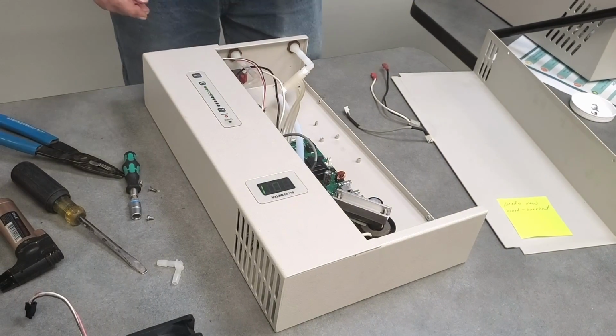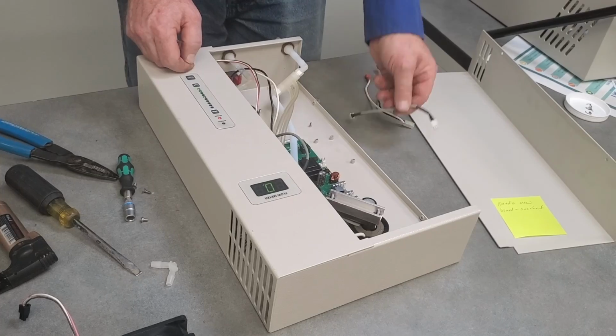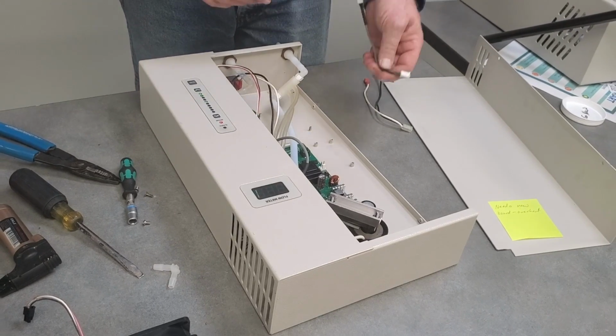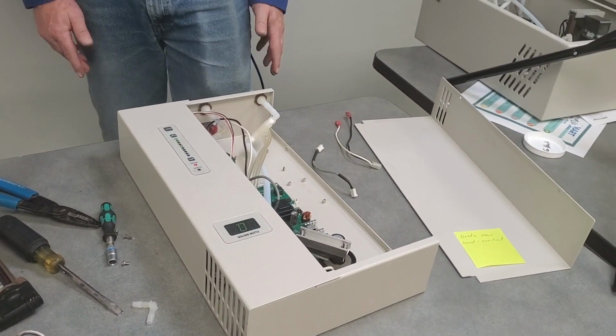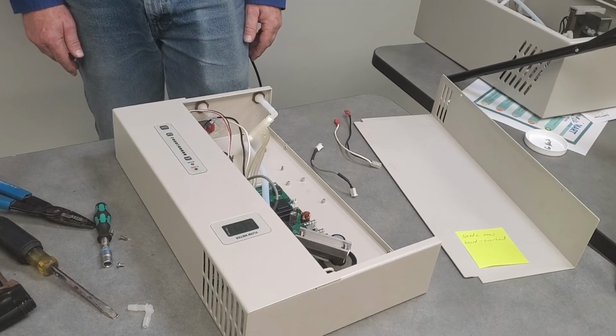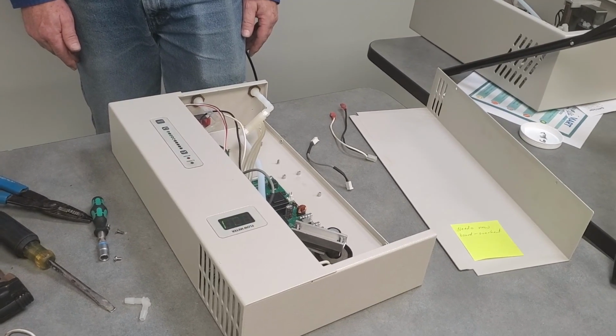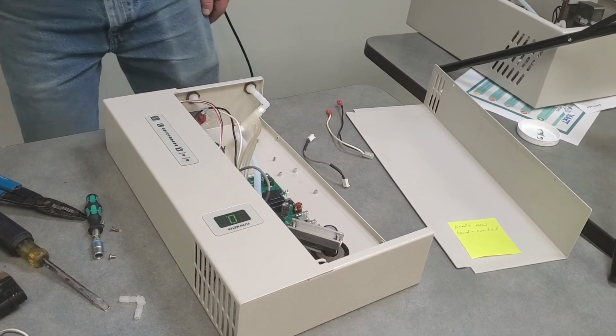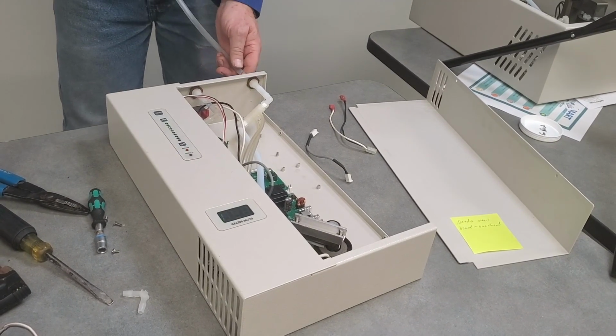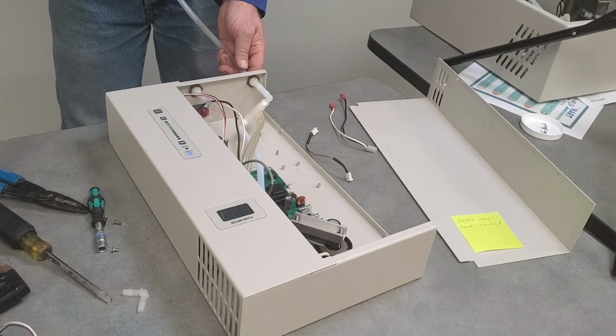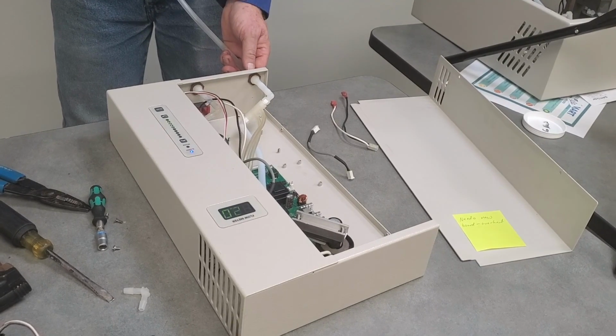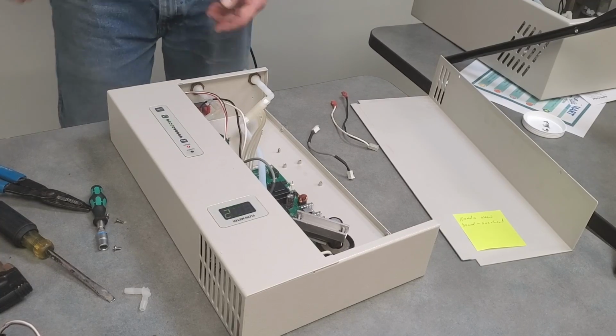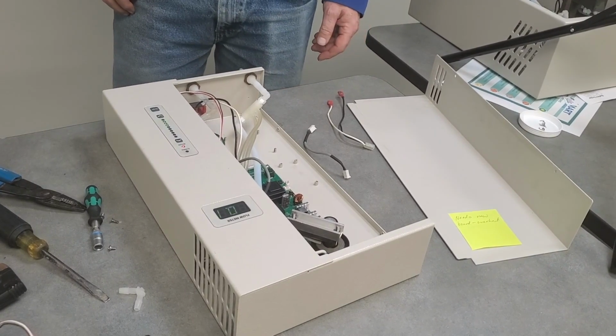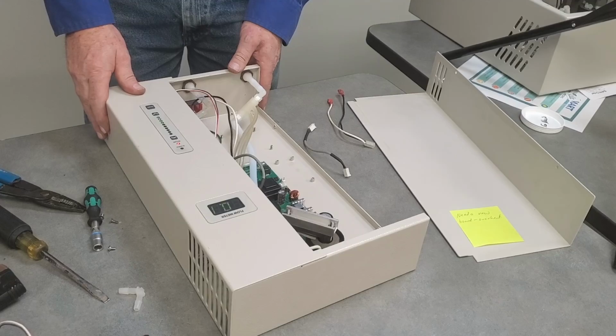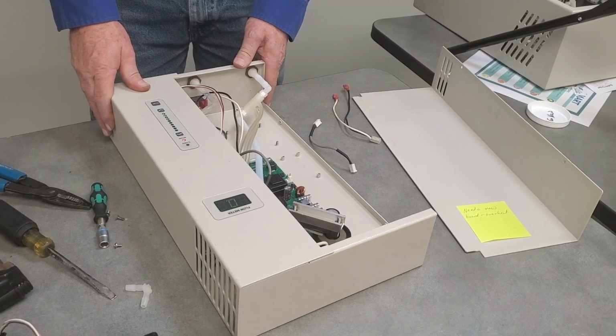Alright, that appears to have solved the problem. So yeah, just a lot of corrosion. Ozone will do that. There's evidence of a lot of ozone leaking in this one. So it's important to make sure we don't have ozone leaking. We'll just double check. Fires right up. Okay, so we're good with this one. We'll clean up some connections, make sure everything's tidied up, and then this one should be good to go.